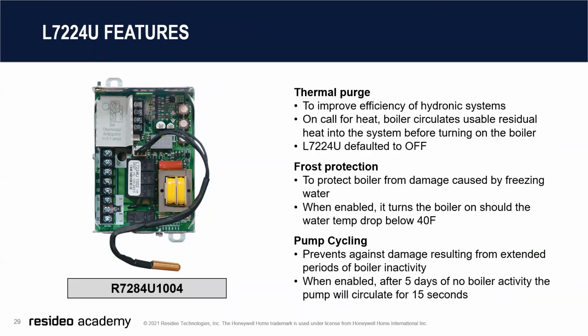It has a thermal purge to improve the efficiency of the hydronic systems on a call for heat. The boiler circulates usable residual heat into the system before it turns on the boiler. You can default it off, but that's an option you can turn on. You can hook it to an outdoor sensor to do frost protection to protect the boiler from damage caused by freezing water. If the outdoor temperature gets below 40, it'll start to fire the burner to protect the boiler. And you can set it up to pump cycle. This prevents damage resulting from extended periods of boiler inactivity. If you enable pump cycling, every 5 days of no boiler activity, the pump will circulate for 15 seconds to try and help keep that pump from seizing up.